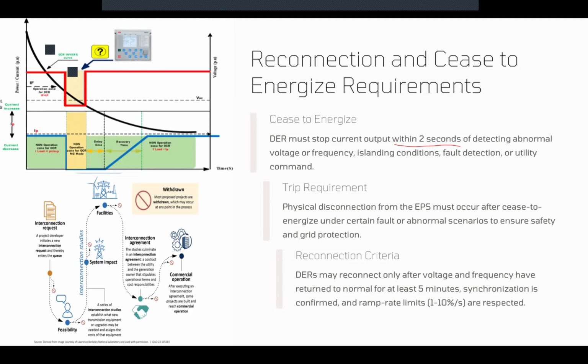Now, the tripping, which is the physical disconnection from the power system, should happen after the cease to energize, after that 2 seconds, under a certain fault or abnormal condition or safety issues. So we said there is a voltage or frequency fluctuation outside of the ride-through, or a utility command to trip, or the equipment protection function finds out that there is an abnormal situation or a fault that could endanger the equipment itself. So tripping the DER is better than losing the DER. These are the conditions under which the DERs are allowed to trip.